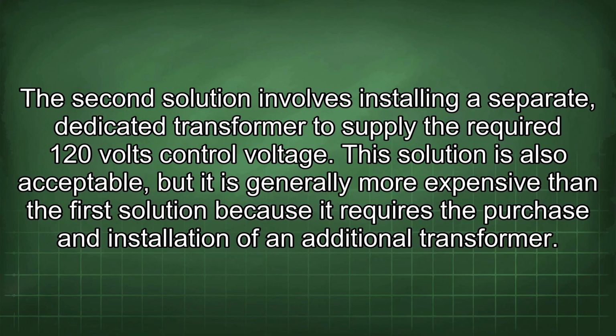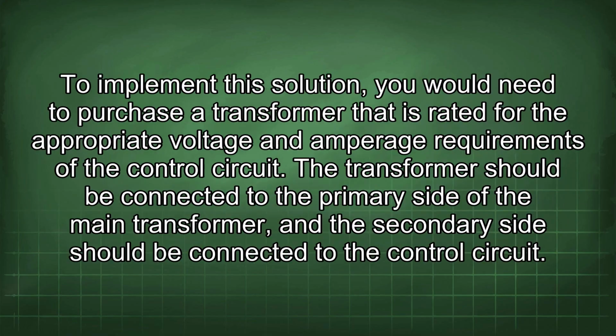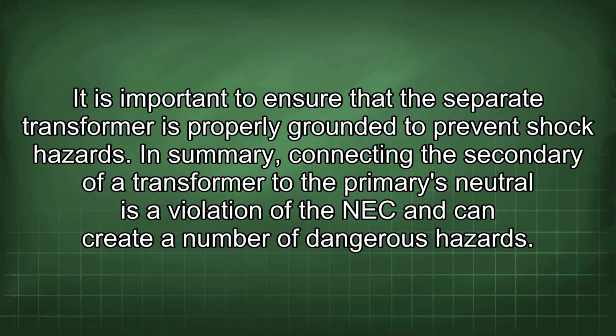The second solution involves installing a separate dedicated transformer to supply the required 120 volts control voltage. This solution is also acceptable, but it is generally more expensive than the first solution because it requires the purchase and installation of an additional transformer. To implement this solution, you would need to purchase a transformer that is rated for the appropriate voltage and amperage requirements of the control circuit. The transformer should be connected to the primary side of the main transformer, and the secondary side should be connected to the control circuit. It is important to ensure that the separate transformer is properly grounded to prevent shock hazards.